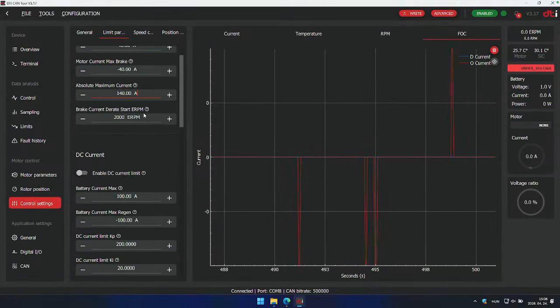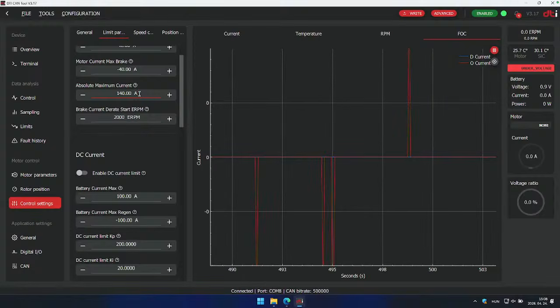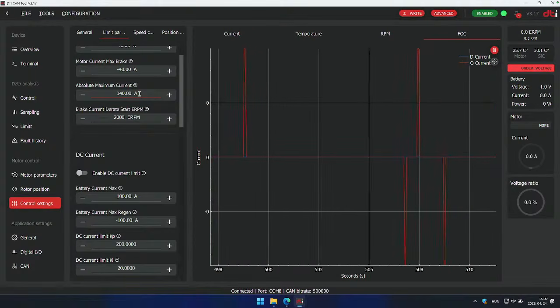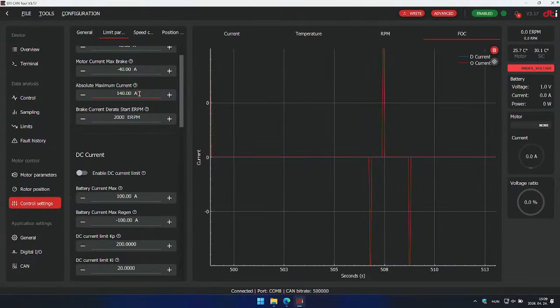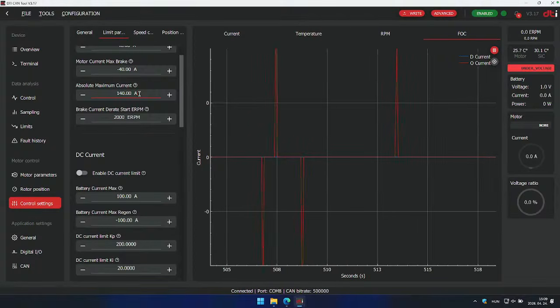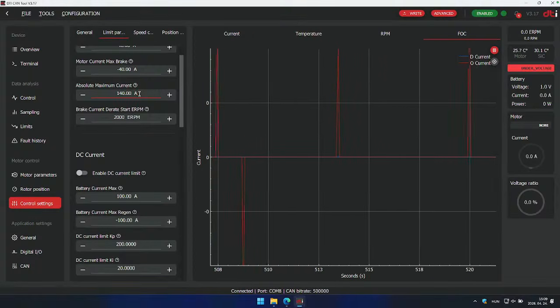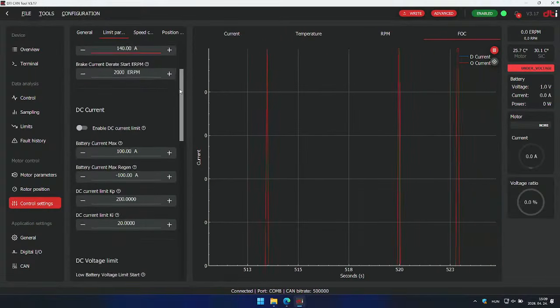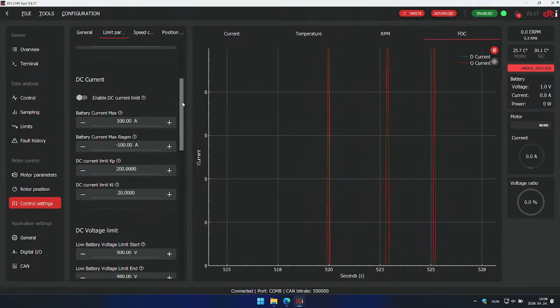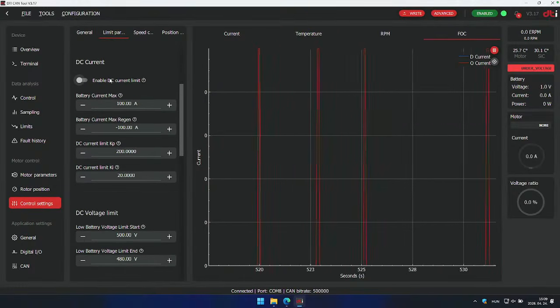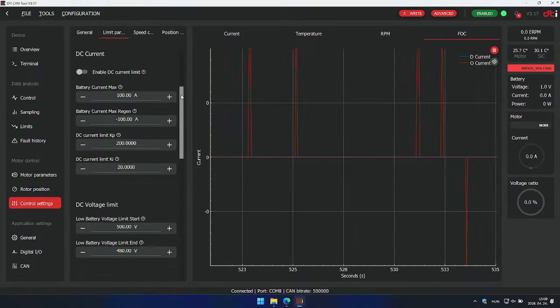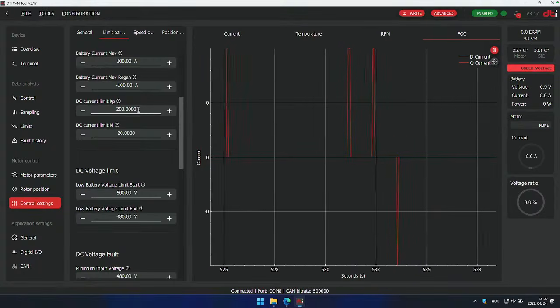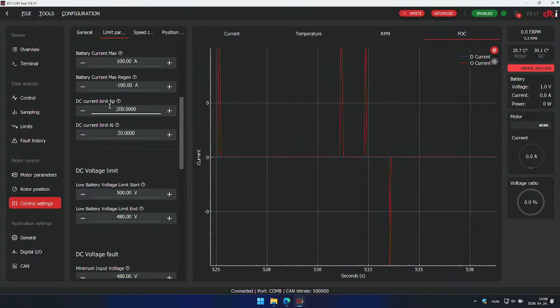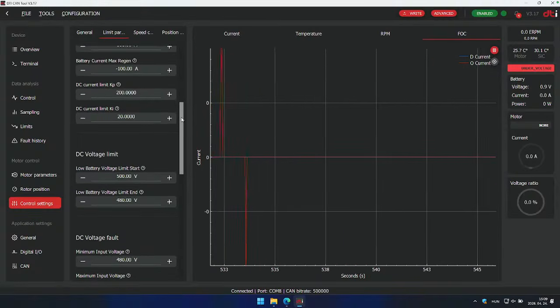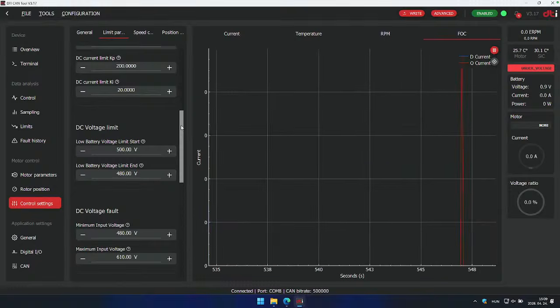We have the absolute maximum current here, which is a fault protection. If the current controllers are mistuned, or there is any fault which causes the current in the motor to be higher than this number, then the inverter will stop the PWM modulation immediately. We have the DC current limit here. You can enable or disable it, and you can type here the maximum DC current you want to input to your inverter. This is a PI current controller, with a KP and KI value, and you can change them if you feel some oscillations or transients.